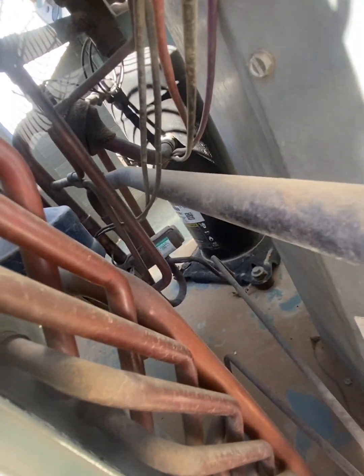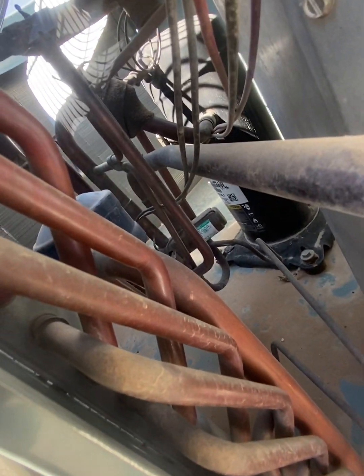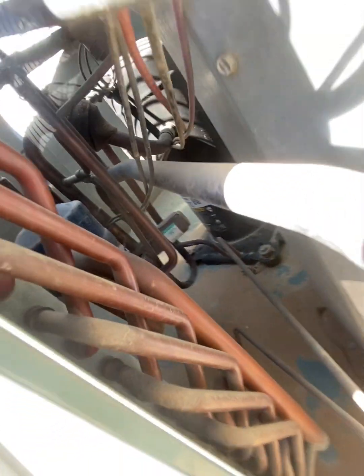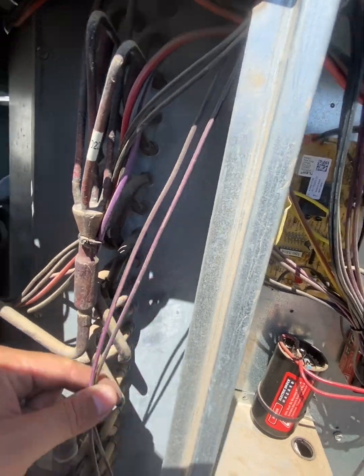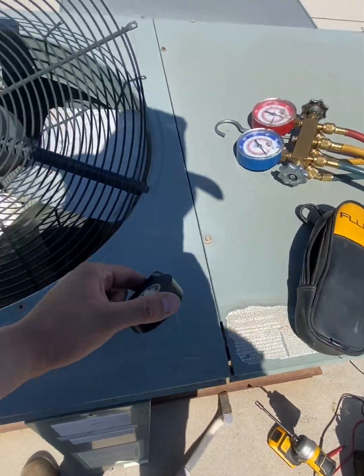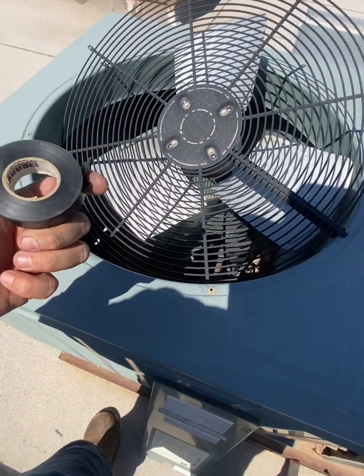Check all the low voltage wires: the reversing valve wires, the high pressure switch wires, and the low pressure switch wiring. Make sure that it's not rubbing against anything. Make sure that the insulation is not cracked or broken and it's not touching the copper. If you do find a damaged area, just go ahead and wrap it with electrical tape.